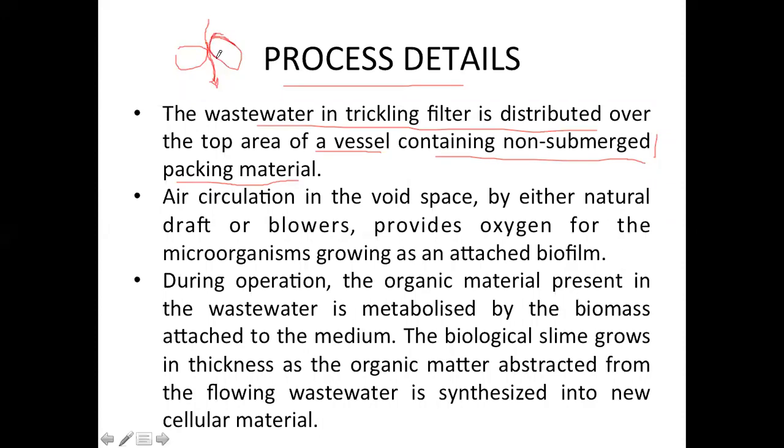of the gravel. At the surface of the gravel there will be development of biomass, or microbes, on the surface of the gravel packing. So the whole trickling filter body is filled with this gravel packing, and whatever wastewater comes will pass through these packings. This is an aerobic process. The trickling filter is an aerobic process.